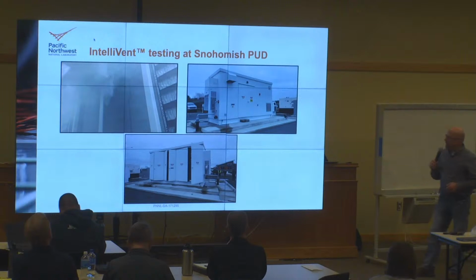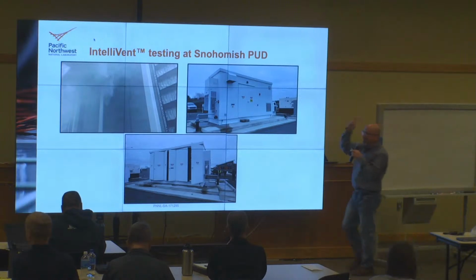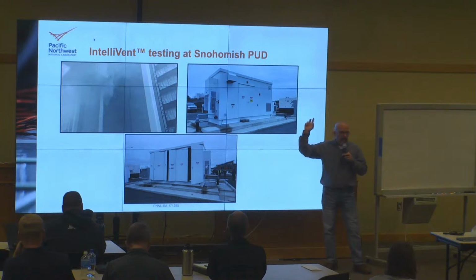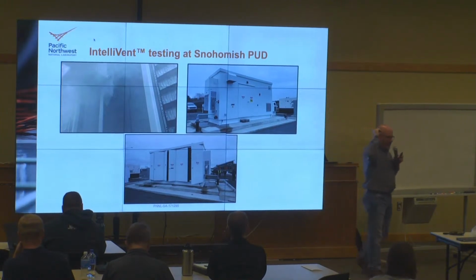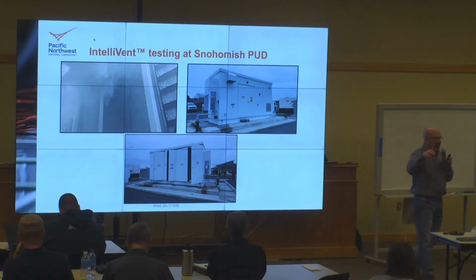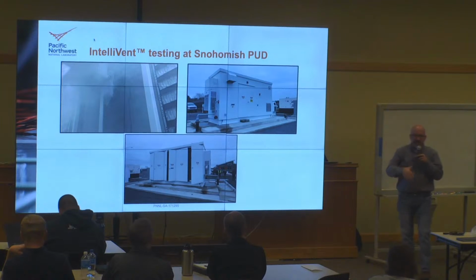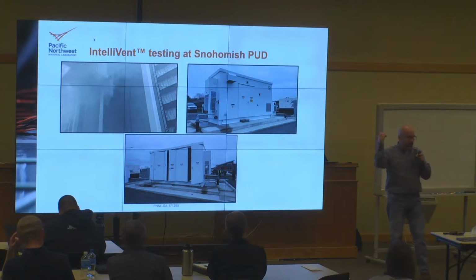So Snohomish PUD, when they first designed this battery system, reached out to us and asked, what is the gold standard of safety for an energy storage system? What's available to use? We said, well, there are some new off-gas sensors out there that sense the electrolyte at that first stage of venting. There's VESDA, very early smoke detection, an aspirating smoke detector. There are exhaust fans, deluge sprinkler and clean agent. So they put all of that in this cabinet.